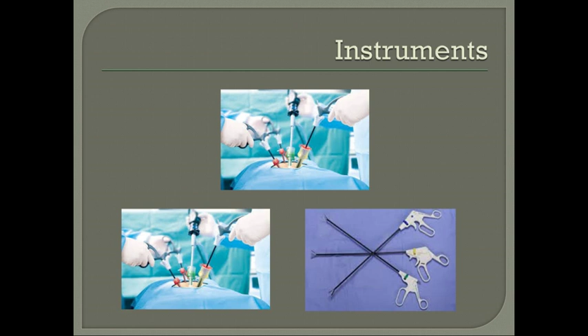You want to make sure that the camera lens is clear and the light cord is functioning properly. If the lens has scratches or the fiber optic light cord inside is cracked, the view inside the cavity will not be as crisp and will make it hard to see. MIS surgery requires long, delicate instruments, which are limited in their range of motion. Withdrawing and inserting them into body cavities can be awkward.